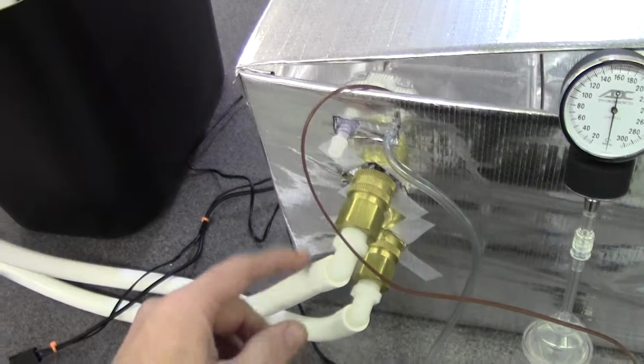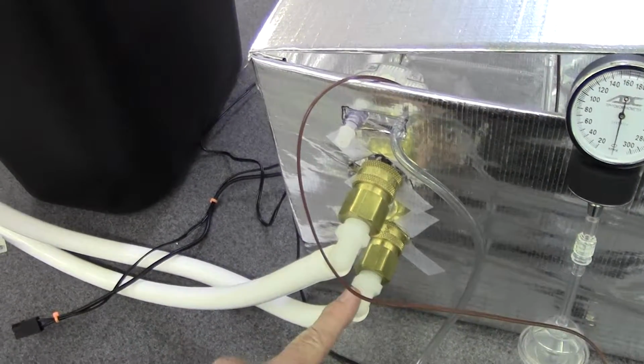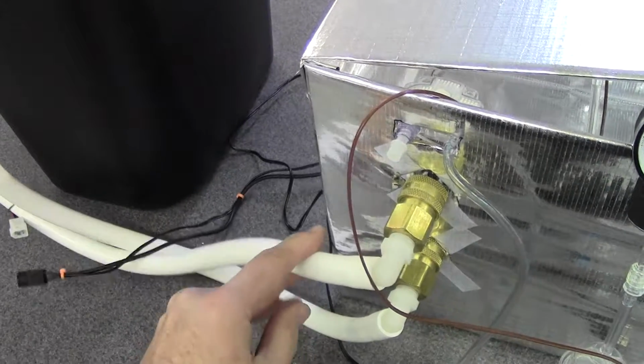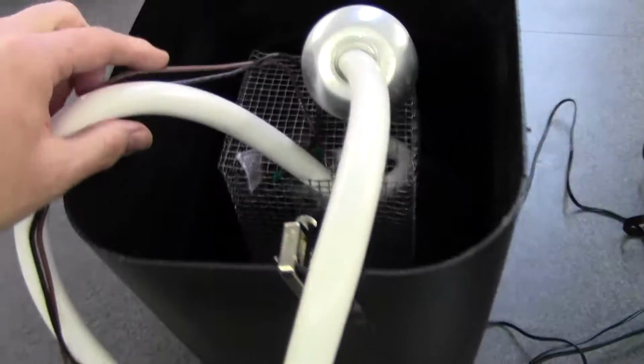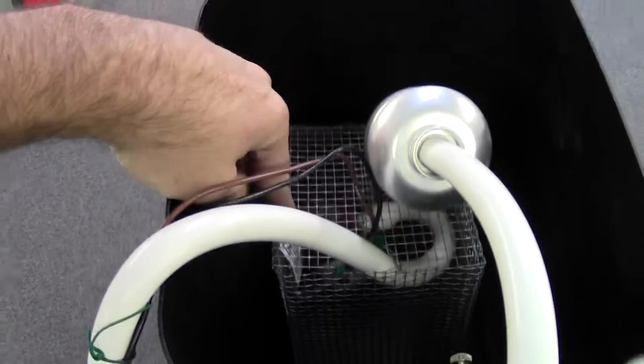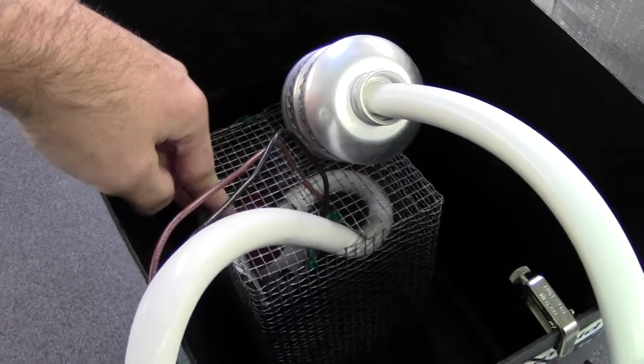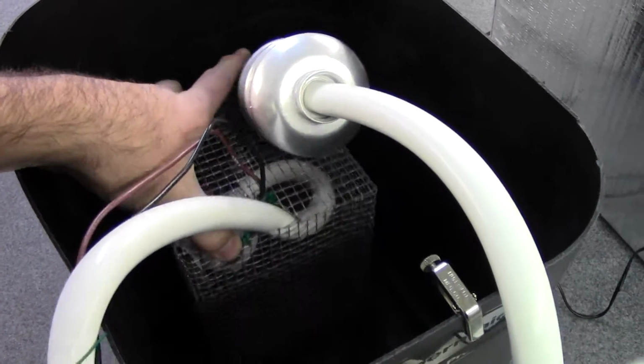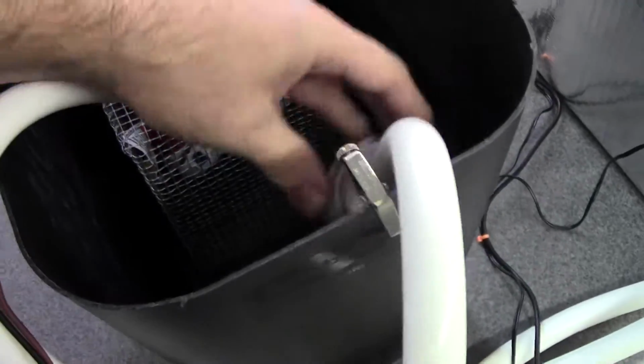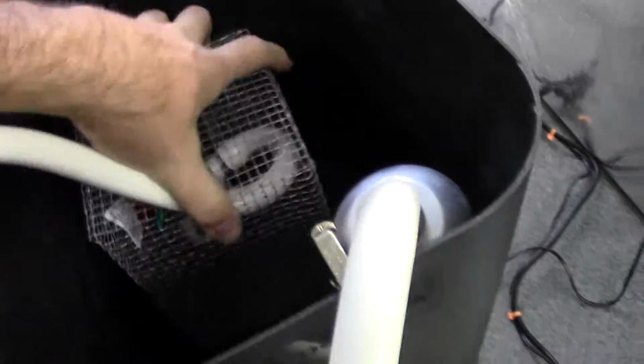The heat exchanger on the other side, this is the inlet is the top, the outlet is the bottom. The inlet is the pump side, and the pump is inside of a protective cage so that ice crystals don't get into the intake. And that allows the liquid to get to the bottom of the pump a little easier inside there.